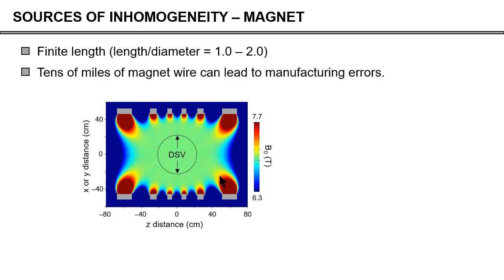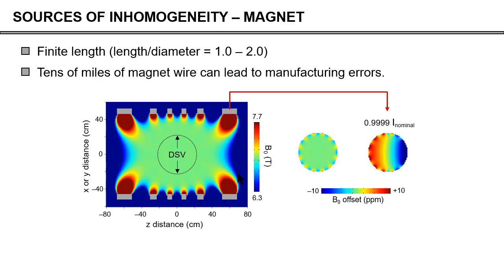This is a typical magnet — a six-coil design for seven Tesla. You can see that within the diameter spherical volume, or DSV, your magnetic field is close to seven Tesla. And if you zoom in, if everything is theoretically perfect, the homogeneity can actually be very, very good. However, even small imperfections — let's say that this outer coil, the number six coil, has 99.99% of its nominal current — that immediately introduces a 20 ppm inhomogeneity. So very small imperfections can lead to very large inhomogeneities.